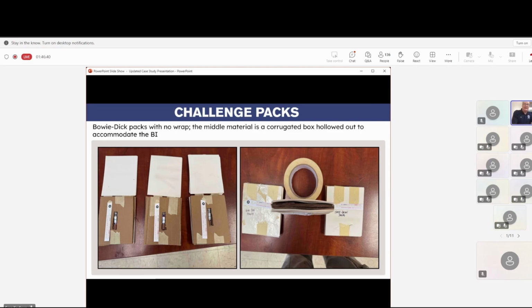This is the challenge packs that I did. I took the Bowie Dicks, took the wraps off. You can see where I have the proper steam strips right there by the biological indicators. In the second slide, you see how it sandwiches in there. On 3 of the cycles, 6, 7, and 8, I actually sealed this down. They were on a hinge. And then for 3 of the cycles, to really make it challenging, to make it denser and harder, I actually taped it down tight to make it very, very dense. These were my challenge packs, and I think you're going to be surprised.